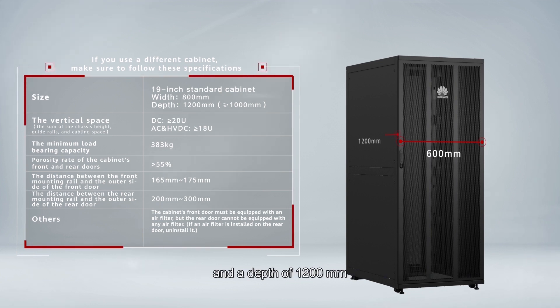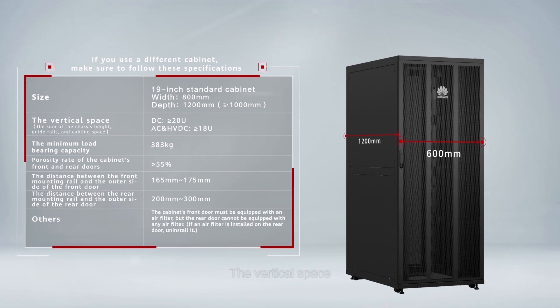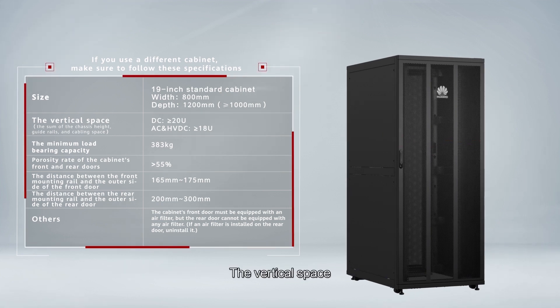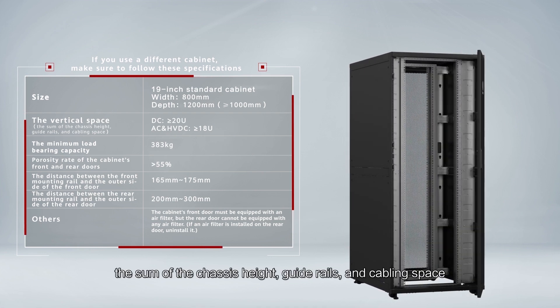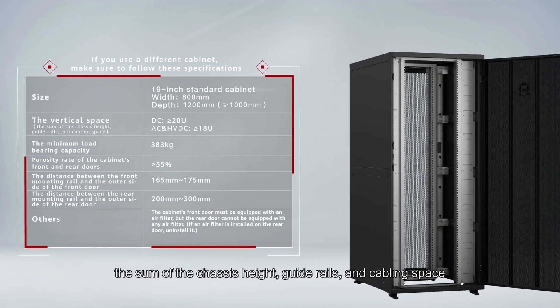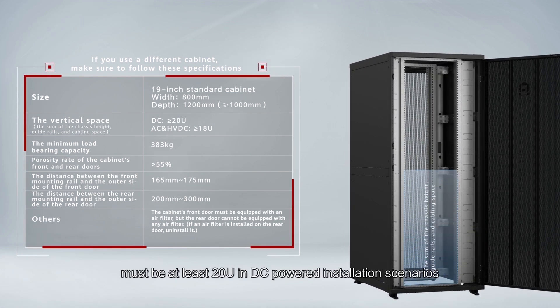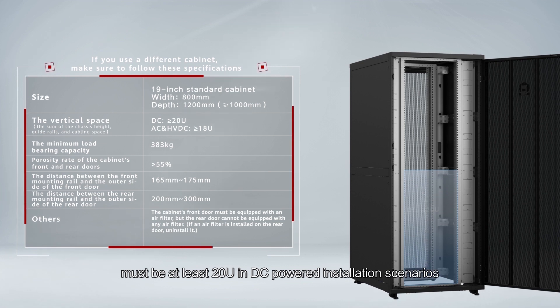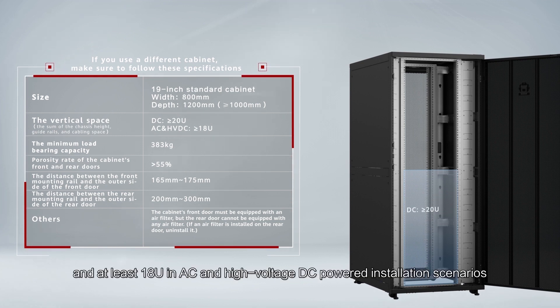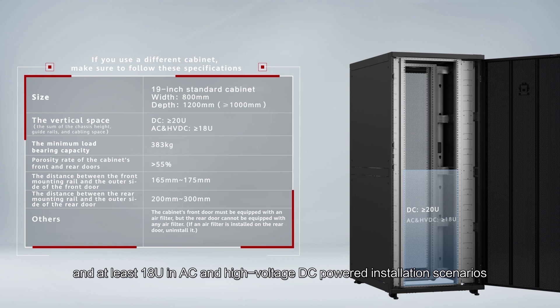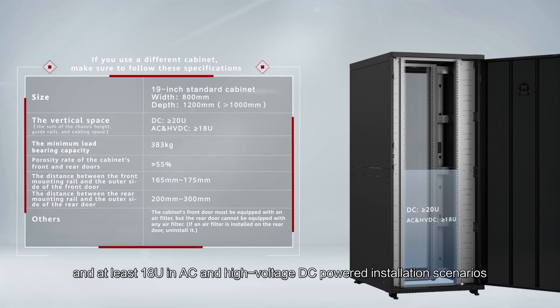Regarding vertical space, the sum of the chassis height, guide rails, and cabling space must be at least 20U in DC-powered installation scenarios, and at least 18U in AC and high-voltage DC powered installation scenarios.